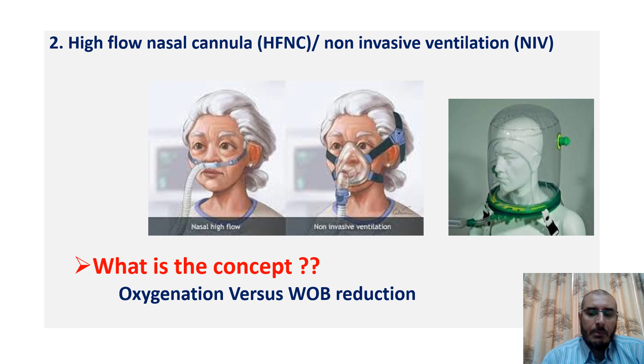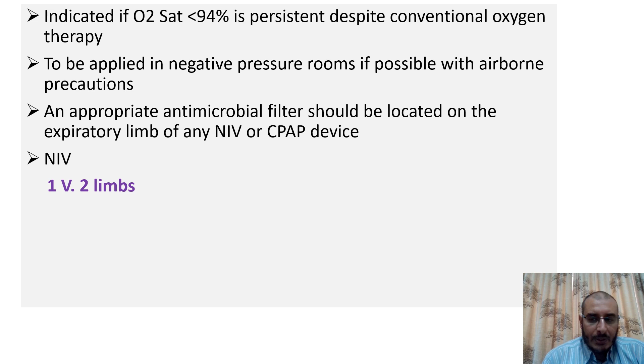Actually, it's indicated for non-invasive ventilation, of course, if the saturation is less than 94 and you cannot achieve your target. It's definitely an aerosol-producing procedure, so it should be done in a negative pressure room with all precautions for airborne precaution from the staff. An appropriate antimicrobial filter should be located on the expiratory limb of the non-invasive or CPAP to reduce the spread of infection.